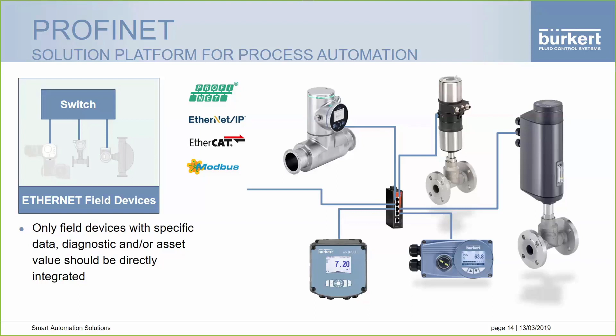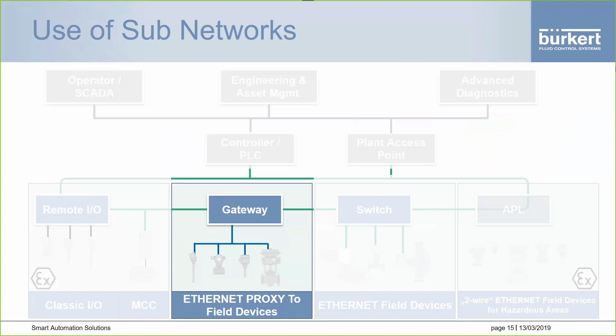The next type is gateways, also known as proxy devices, where we swap from one network to a secondary network that talks at the field level. There are multiple sub-networks that operate under Ethernet - ASI is one of the big ones, and soon ASI 5 products will start rolling out. We also have IO-Link, CAN-Open, Profibus, and a sub-network we call büS, which is the integration of our own field devices. There are many networks and many ways to use them when it makes sense.